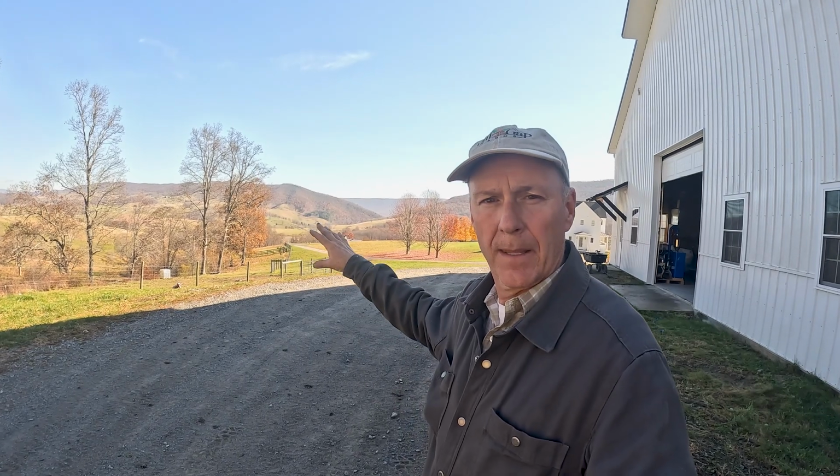However, when we opened up the valve here the other day to see if we could water the cottage and the red barn, it wasn't filling fast enough. Something was wrong, and I wasn't sure what was happening. So I isolated the cottage and the red barn. And when I did that, the only water that was on was for the hydrants.